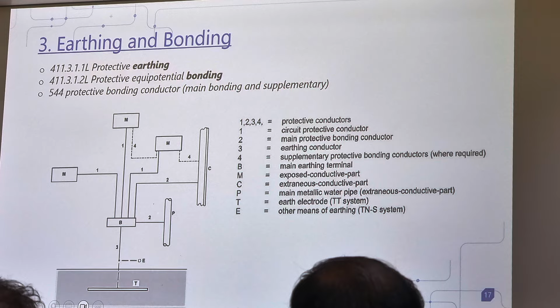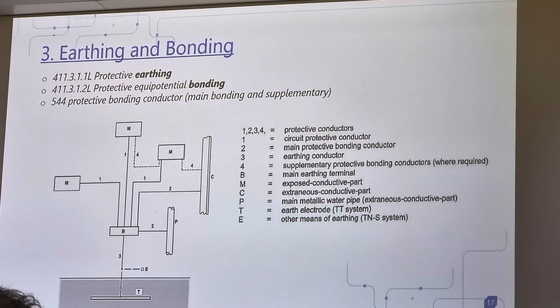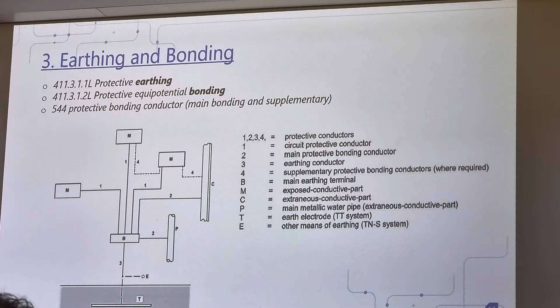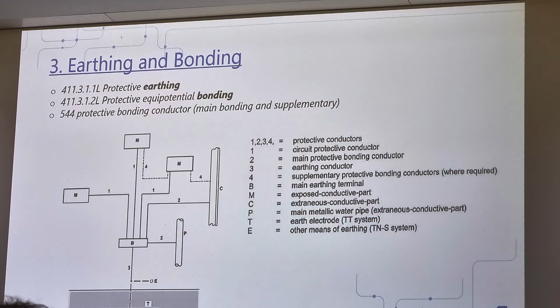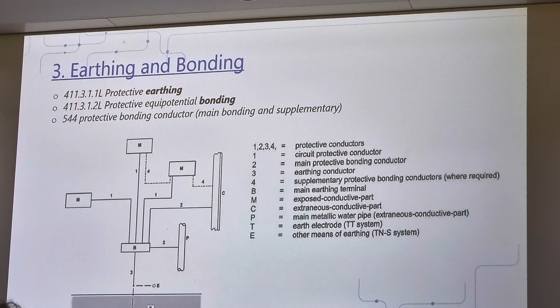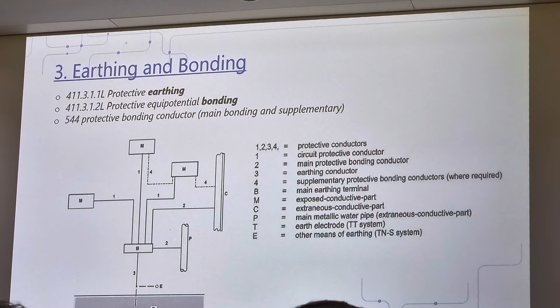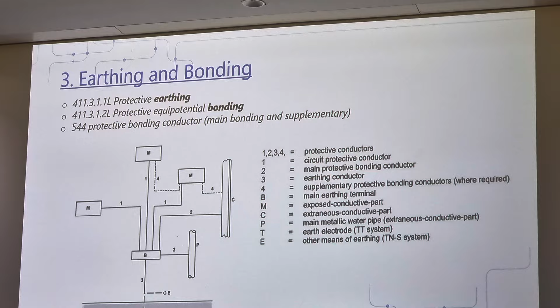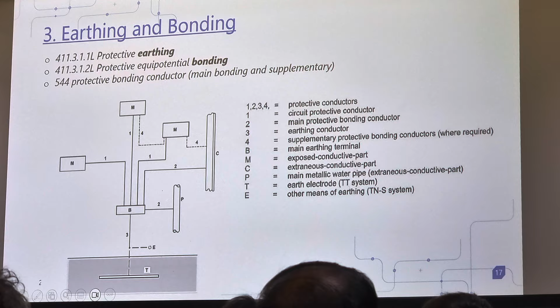What kinds of earth? As you know, TN-S system, there's one earth which is a combination of source earth and installation earth. In the TT system, then you have two earths which has a source earth as well as the installation earth. So 411 talks about all different kinds of earthing. So it will affect how you provide protective systems in the design. On top of that, you need to have equipotential or protective equipotential bonding. So this diagram shows you what is earthing, what is bonding. They serve different purposes, but they must work hand in hand.